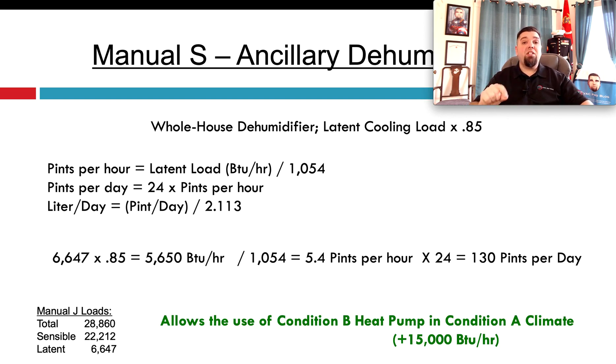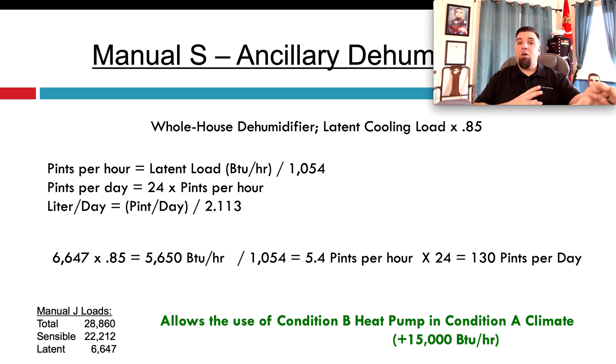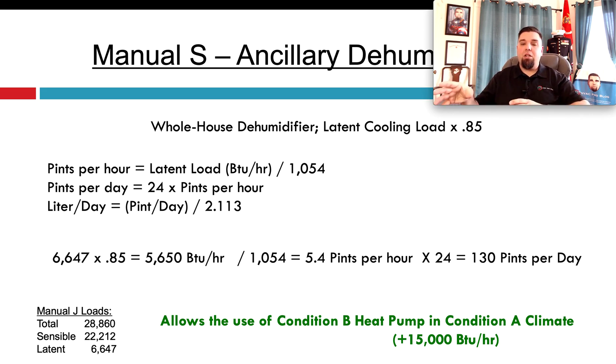With ancillary dehumidification installed, you are allowed anywhere in the United States to use Condition B for heat pump selection. So if you're in a warm climate and need to oversize the system to get the BTUs needed — which could be up to plus 15,000 BTUs over the total cooling gain — you can address the latent needs with a whole-house dehumidifier. That way, an oversized system in that application isn't a problem because the dehumidifier is removing the moisture.